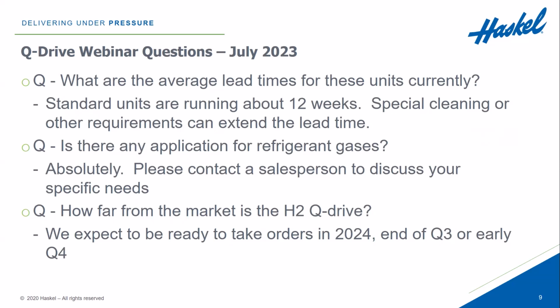Are there any applications for refrigerant gases? Absolutely. We should be able to handle a variety of just about all refrigerants. Our standard seal materials in there are Viton and ultra high molecular weight polyethylene. We can run different O-rings and seal materials if needed for your specific application.